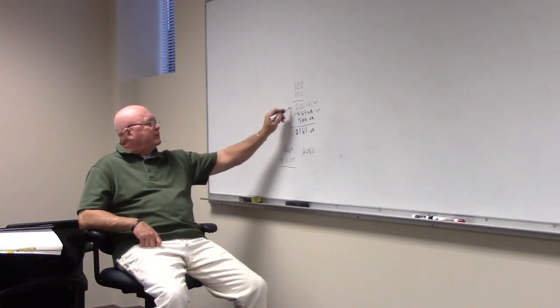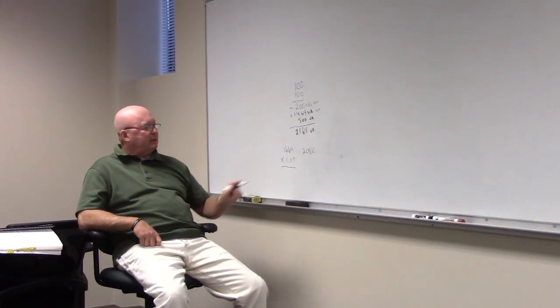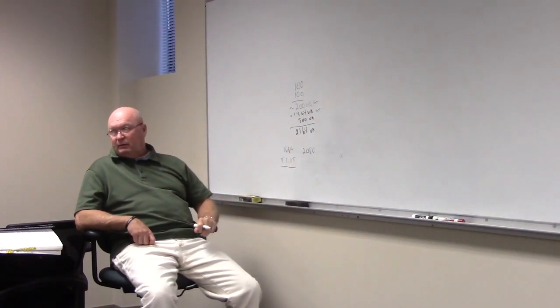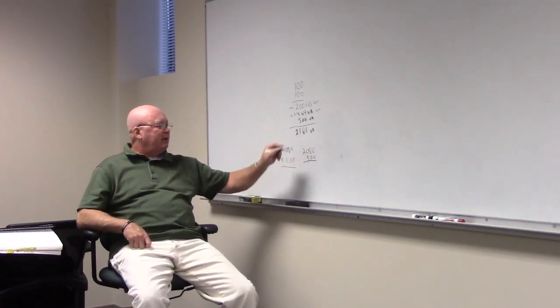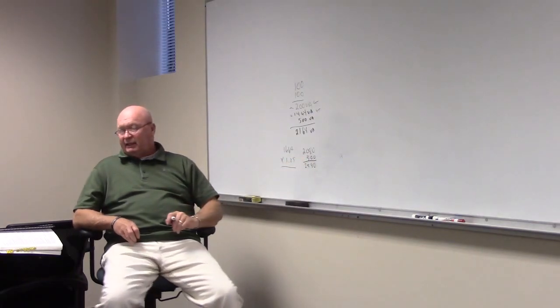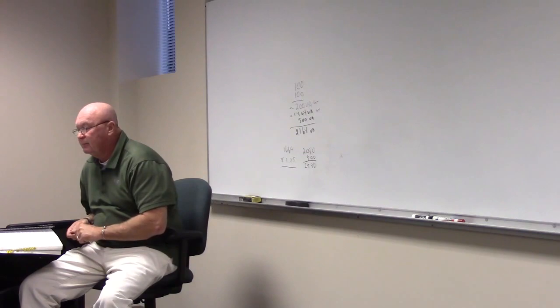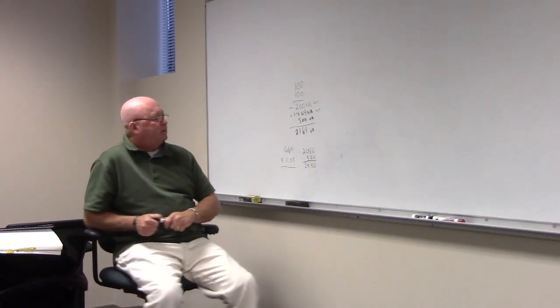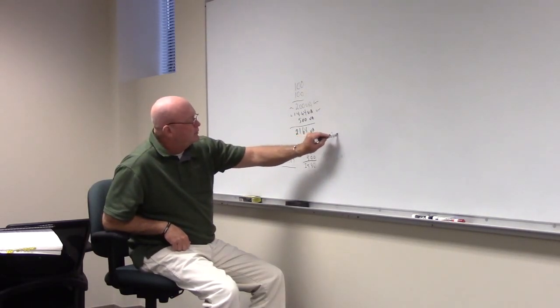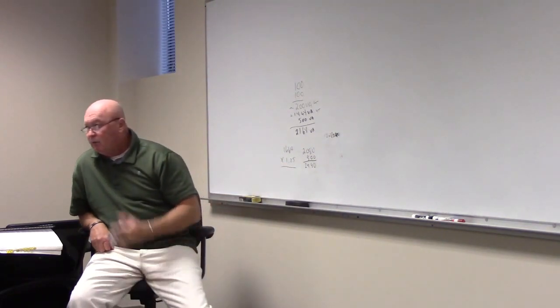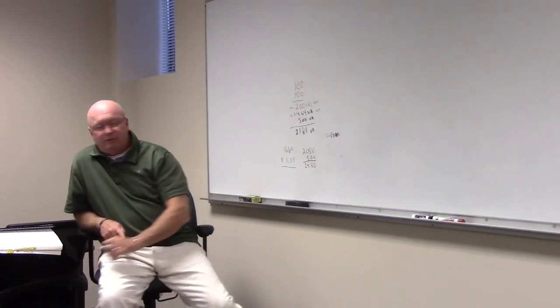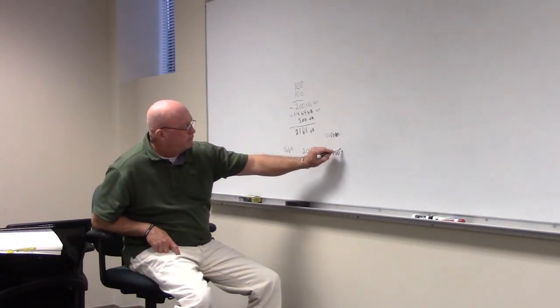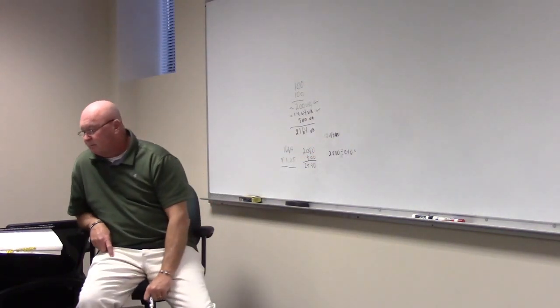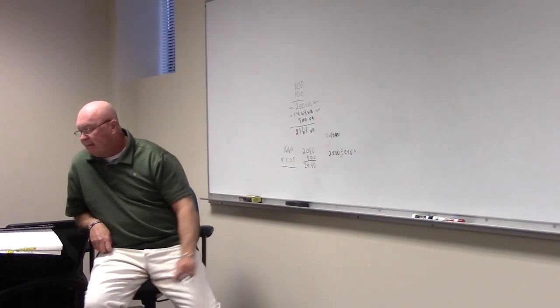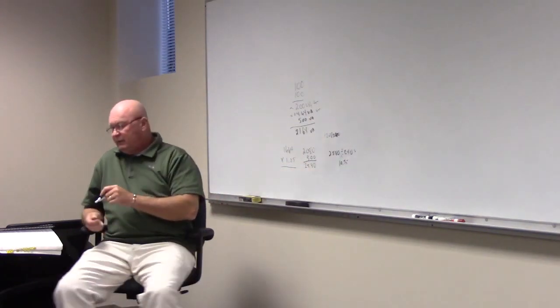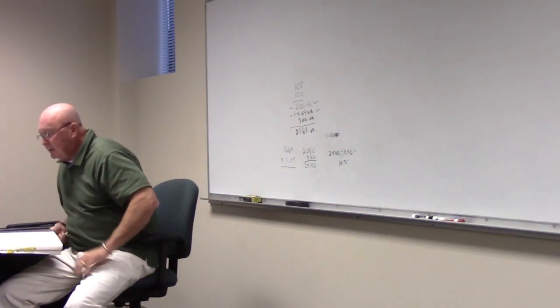What are we going to do with this 2080? This was our continuous load. The only thing we've got left is that 500 non-continuous. So now we're going to add 2080 to what? 500. And so we see our actual load now is not 2164, but it's 2580. That makes sense, guys? Okay. 2580. This is a 120/240 volt service though, single phase. So we're going to take this 2580. What voltage would we divide it by? 240. And we come up with how many amps? 10.75. Yeah, 10.75.